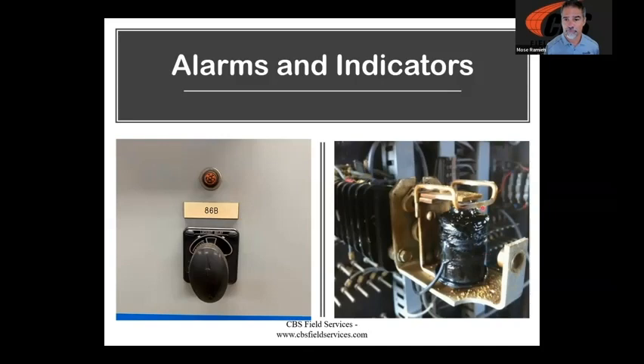Well, once again, nobody knew that he had damaged it, and two, they didn't notice that this trip coil light was out. Now, this light doesn't tie to this coil, they're completely different fuses, but this damage would have showed up as no control light. So just like on our breakers, if you're walking around and you don't see a red light, you see nothing, we don't know that the 86 can operate. And these are critical systems. This is a critical component to making sure that your substation is going to be safe and reliable. Once again, if it doesn't operate, any number of things can go horribly wrong after that.